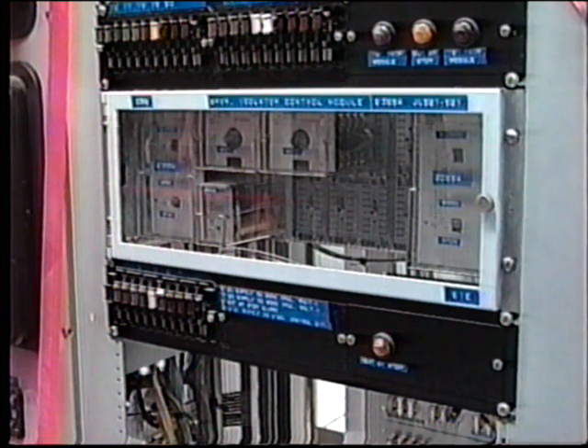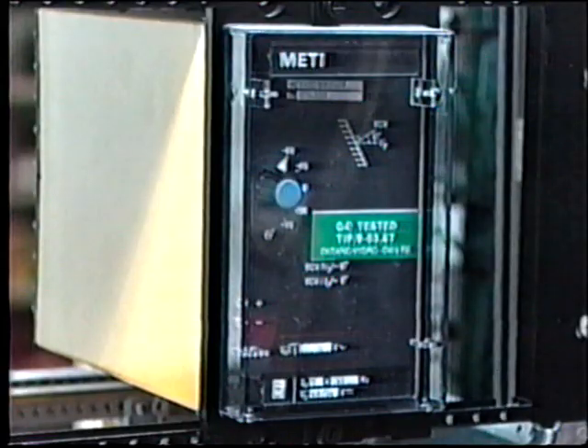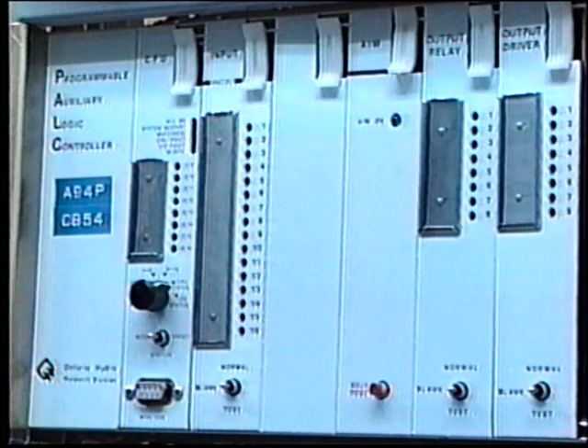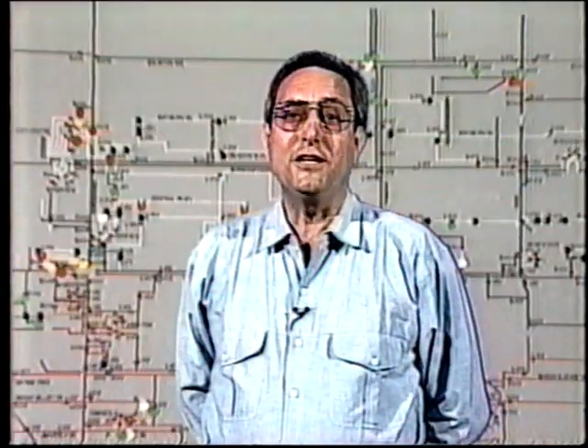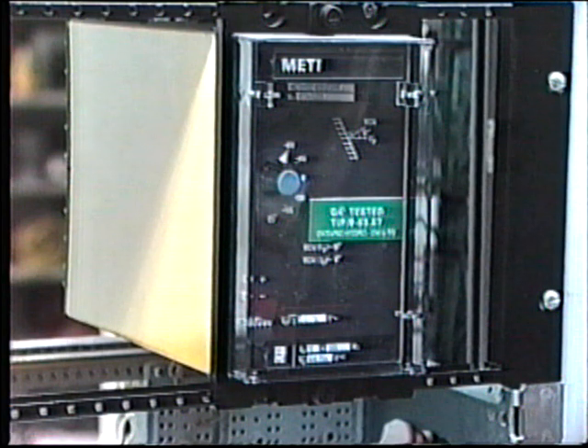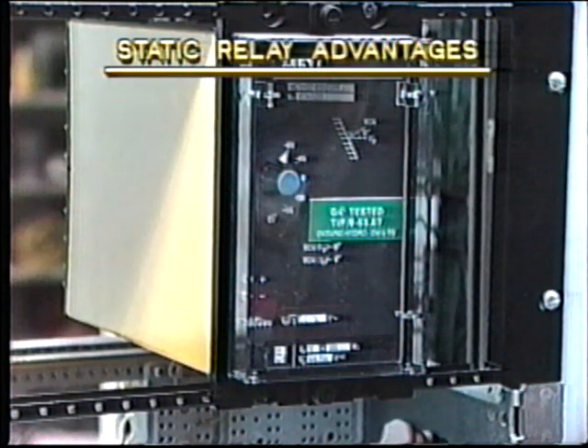However, on more recent installations, you may find static relaying employed. This may be in the form of solid-state relays or microprocessor relays. In this videotape, we'll look at solid-state analog-type relays first. This type of relay has been around for many years, but most power companies have continued to stick with electromechanical relays because of their familiarity and high level of reliability. However, the static relay does offer certain advantages.